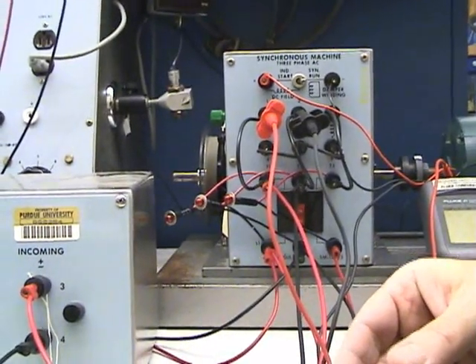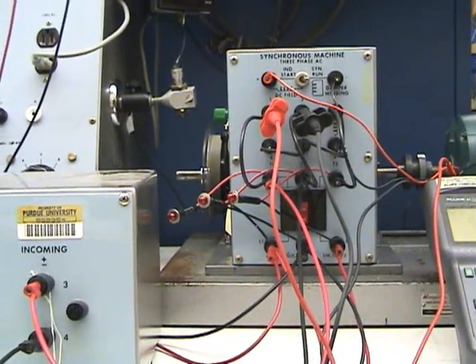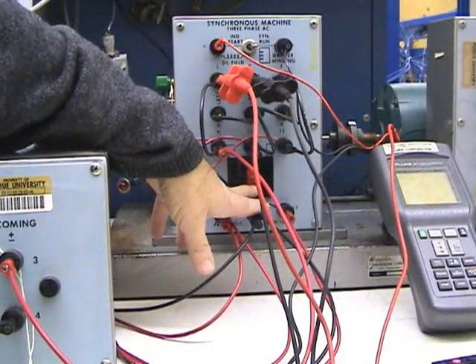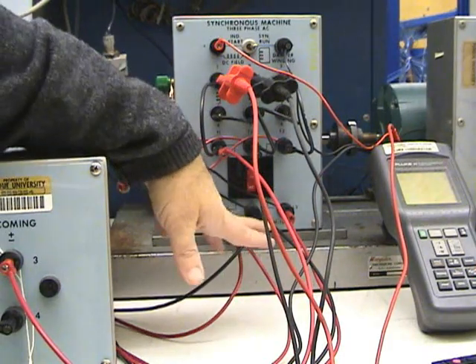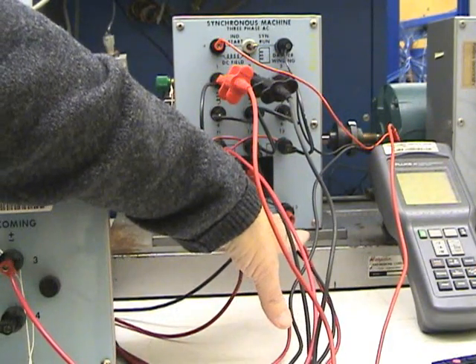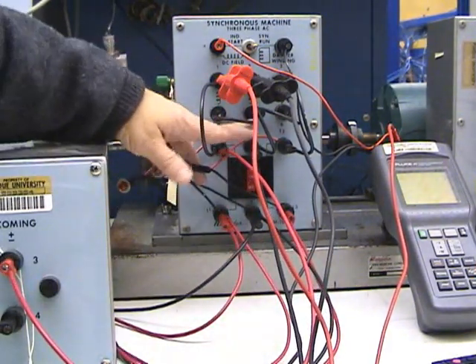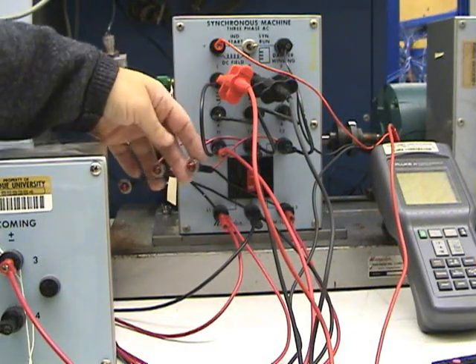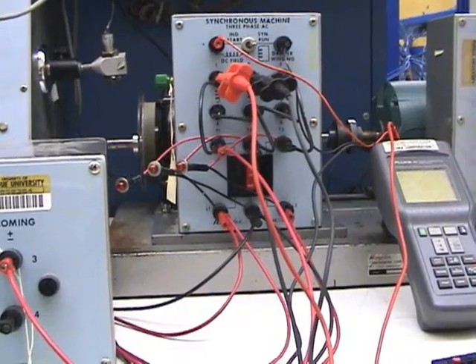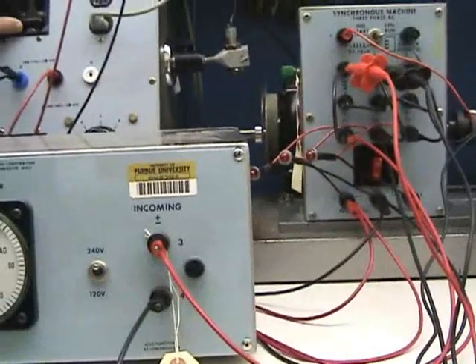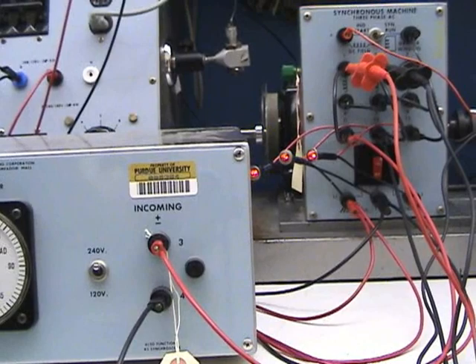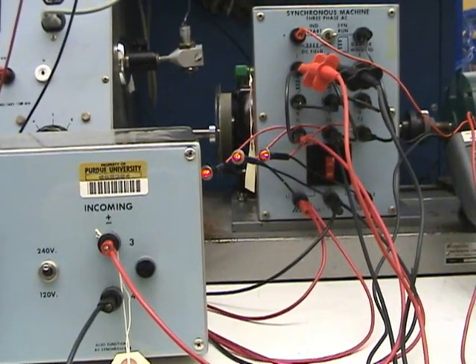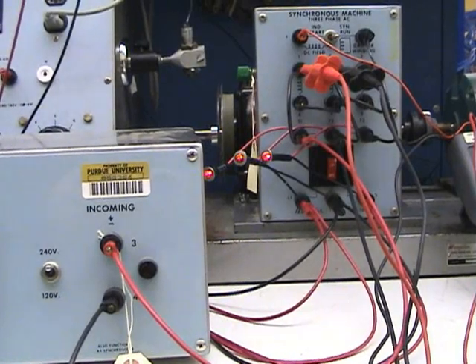So we'll get started here in a second. Before we do anything, the first thing you want to do is make sure the switch on the synchronous machine is off, because you're going to have the power system connected to the bottom of the switch, and you've got the generated voltage at the top of the switch. So make sure the switch is off, the lights are across the switch. We want to turn on the power now. And we notice that the lights are, in fact, lit up as a result of the fact that there's voltage at the bottom of the switch, even though there's none at the top here.